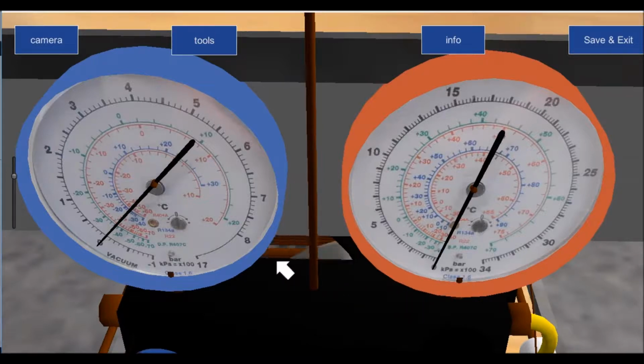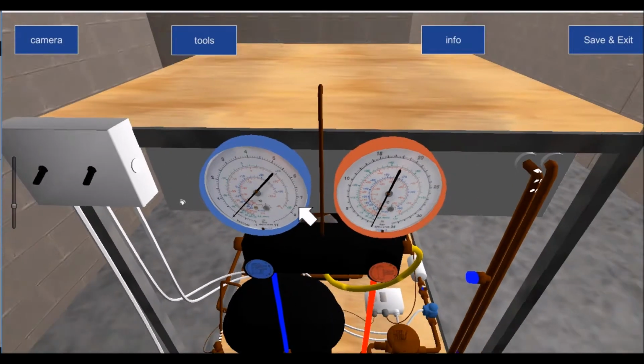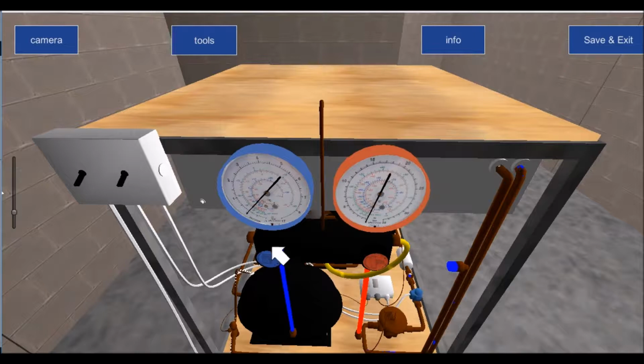And you'll also notice the blue representing the low side versus the red color. That's kind of an American idea, whereby we use red gauge manifolds to represent high temperature, high pressure, and blue gauge manifolds to represent low temperature, low pressure. And you'll notice the blue line coming from the low side of the system to your low side gauge, therefore representing low pressure, and the red line coming from our high side gauge, representing high pressure, high temperature.